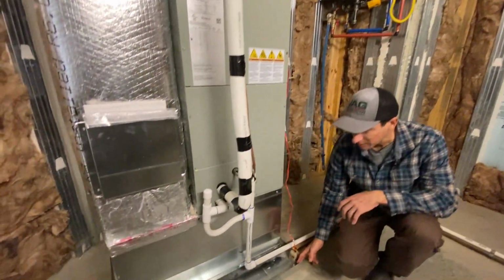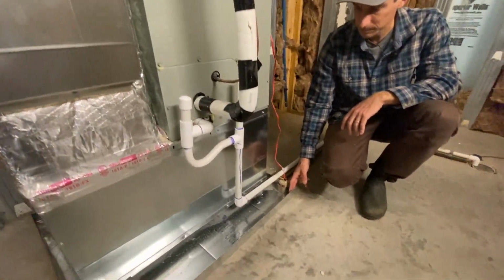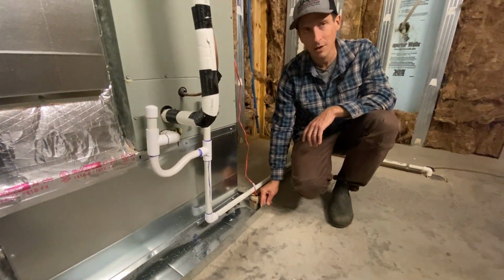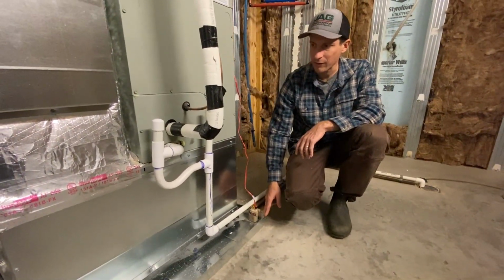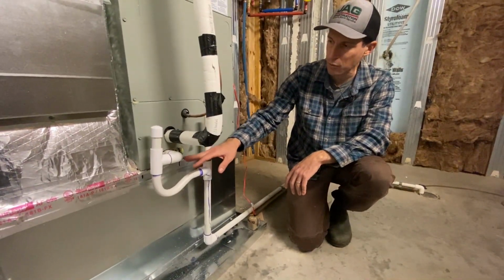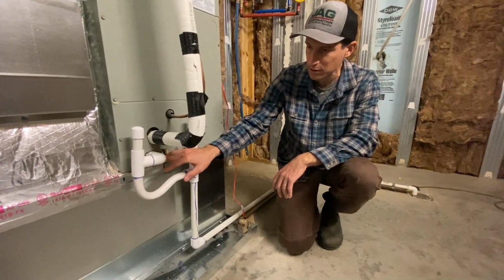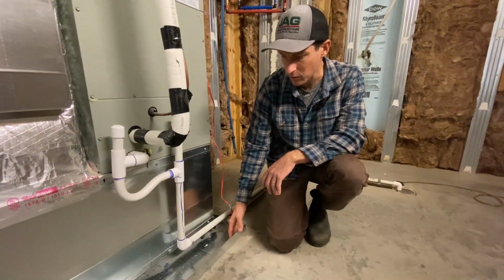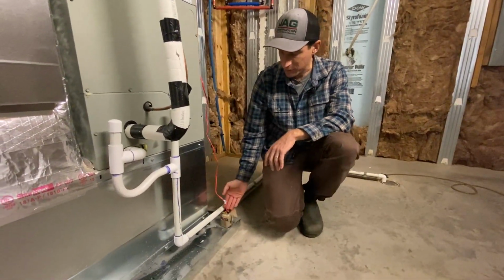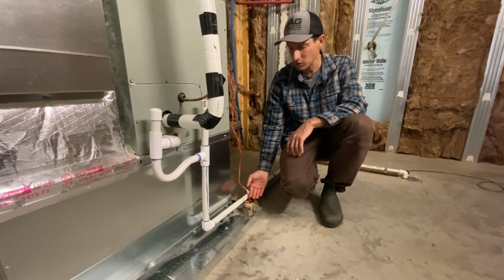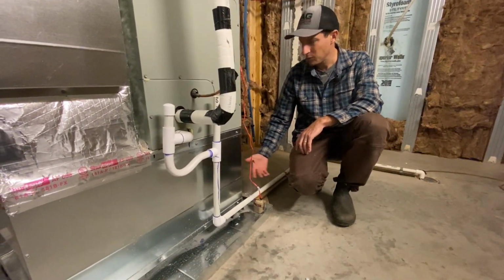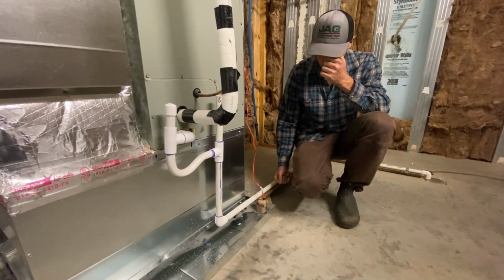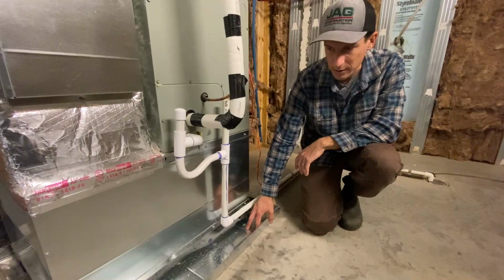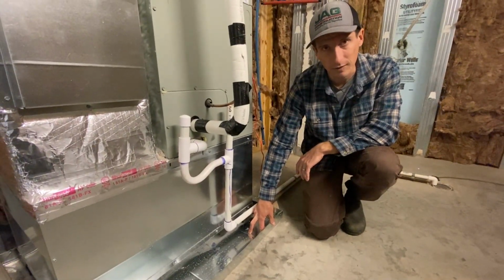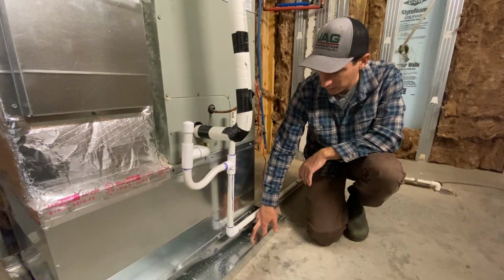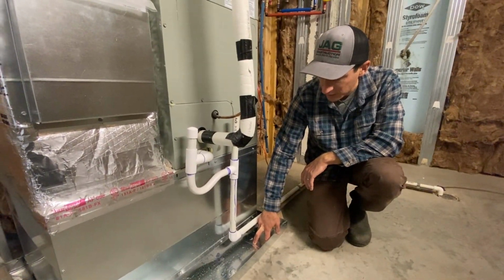There is also a pan underneath the HVAC unit. This pan is sort of a backup to your condensate line. So if there is ever an issue with the condensate line backing up or the pan, the primary pan inside the unit, you have this secondary pan underneath the unit. If this pan fills up with water, there's a switch on it that will shut your HVAC unit off so that it does not flood with condensate down here. So if you ever notice water in your condensate pan, you want to contact an HVAC contractor immediately. That means that something is not right with the condensate portion of your HVAC system.